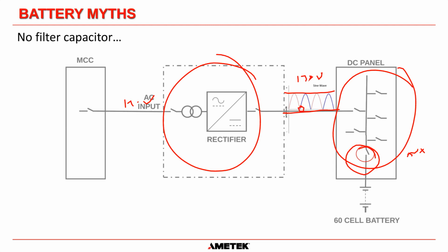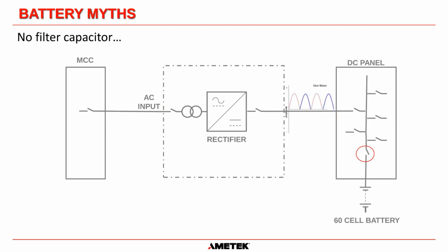So depending on what the tolerance of your loads are, relays could start chattering. That could cause serious issues. So that is why you should never open the battery breaker on a system if it has an unfiltered charger. Even in truth, on a switchgear system, most charger manufacturers sell what's called a battery eliminator.